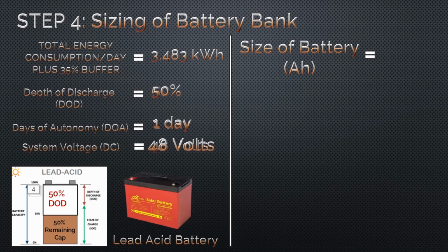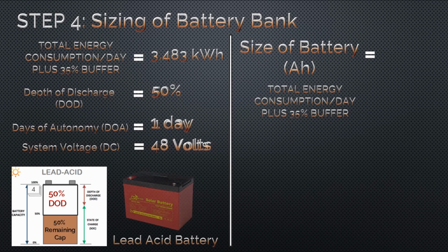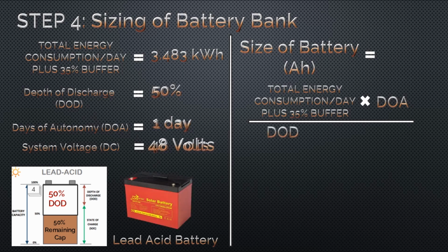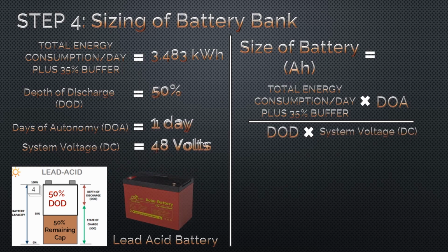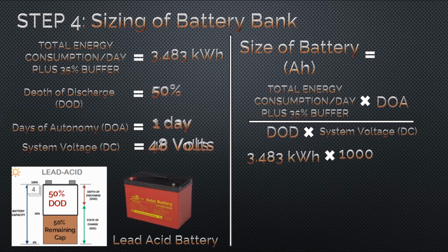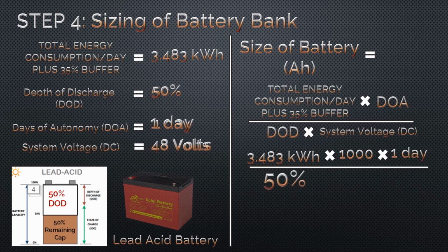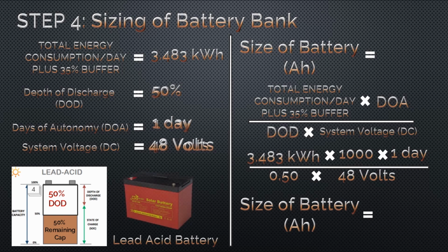Now the size of battery bank in ampere hour is equal to total energy consumption per day, including 35% buffer, times days of autonomy, divided by depth of discharge times DC system voltage, and this is equal to 3.483 kWh, then times 1000 to convert into watt-hour, then times 1 day, then divide by 50%, then we need to convert the percent into decimal, then times 48. So the size of the battery bank is 145 ampere hour. But let's make it 150 ampere hour.